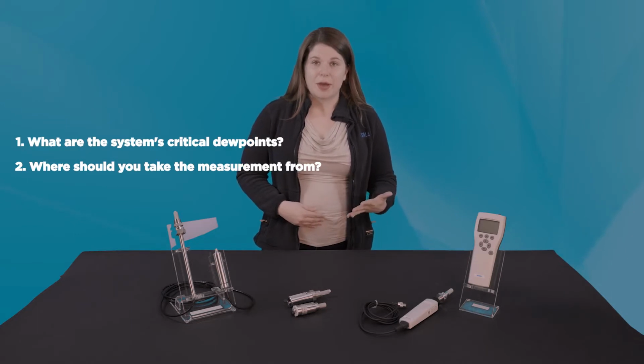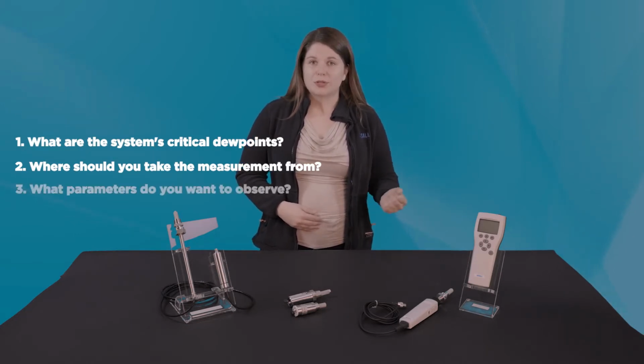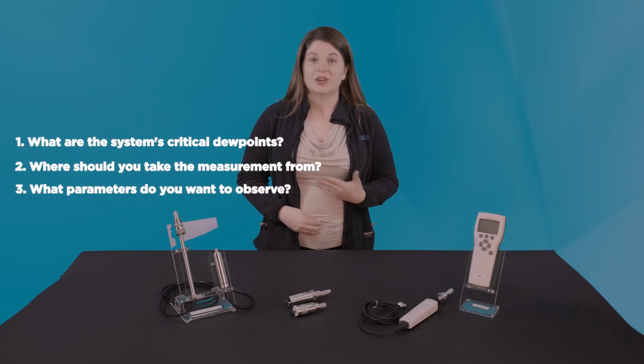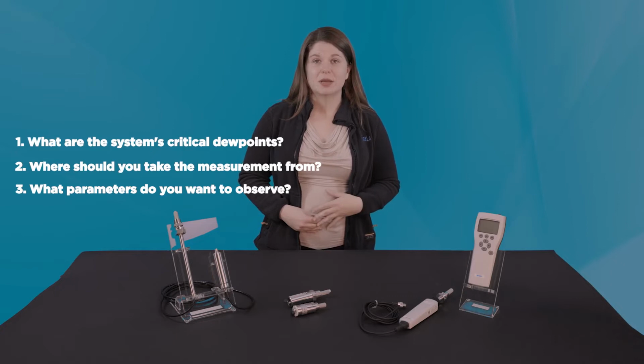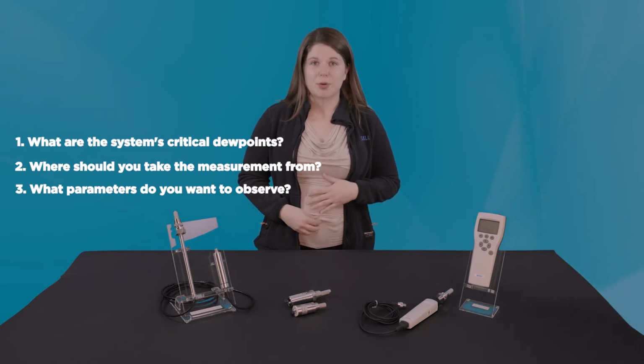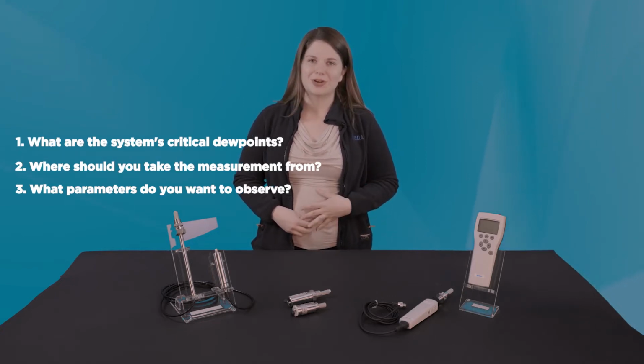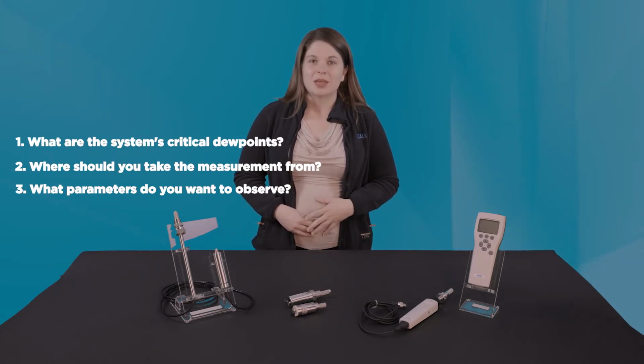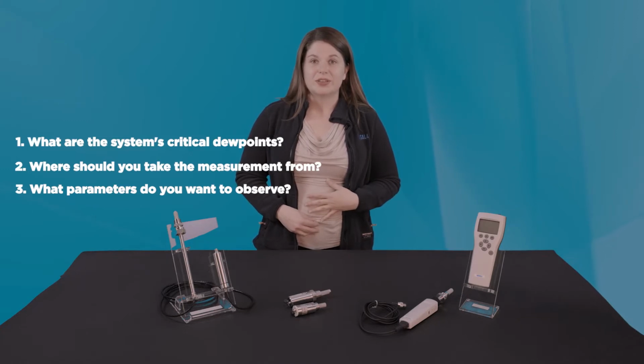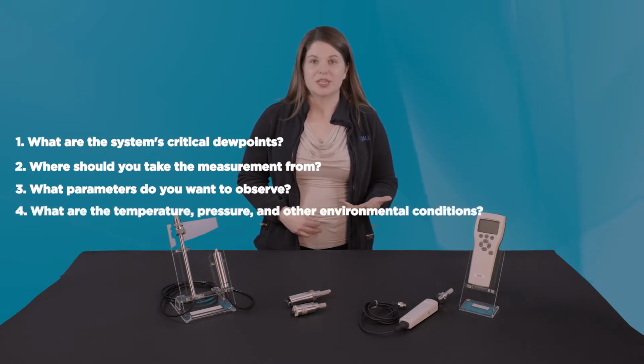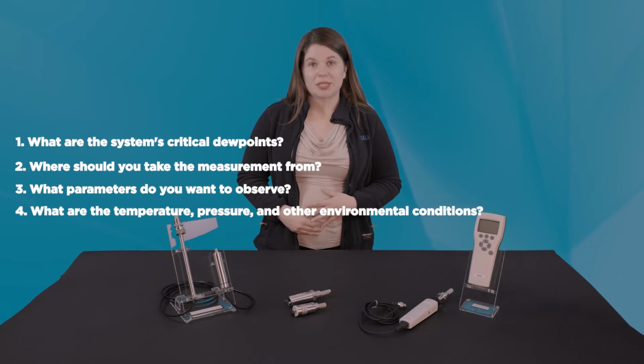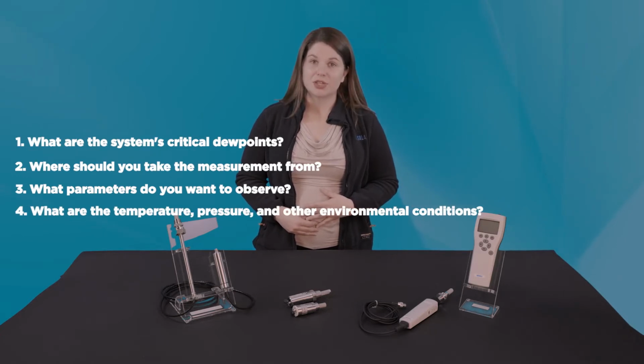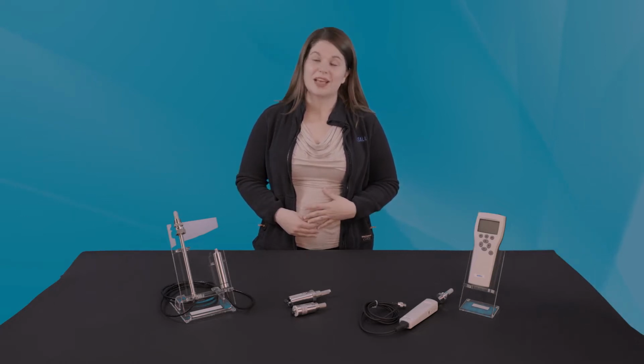Other things to think about will be, what parameters do you want to observe? Vaisala has dew point measurement solutions that can also provide temperature measurements, pressure, and moisture-related parameters other than dew point, like water concentration in ppm or relative humidity. Lastly, you'll also need to consider the temperature and pressure conditions you will see, whether you're looking for a permanently installed solution or something for spot checks, and other complicating factors like chemicals present or use in hazardous areas.